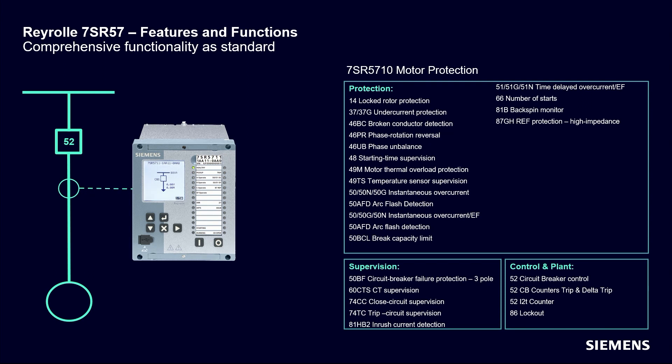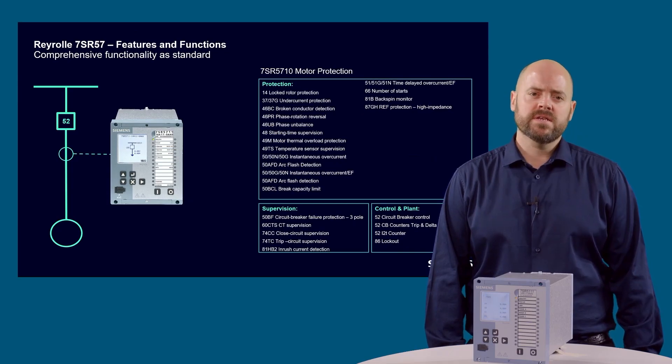Motor starting can be inhibited when the user-defined limit is reached. To complete the scheme application, the device has the option for direct arc flash detection inputs with high-speed tripping contacts for fast clearance when arc faults are detected in enclosed switchgear, and temperature sensor inputs for connection to sensors located in the motor installation.